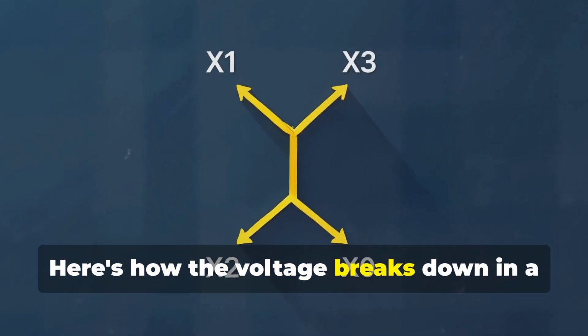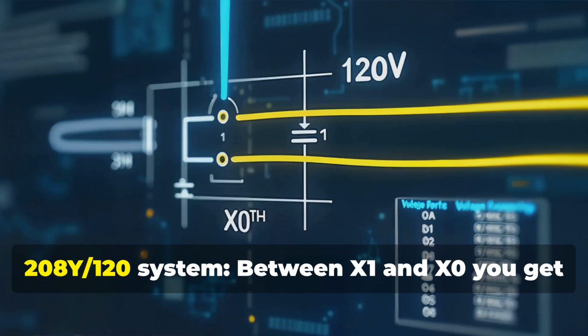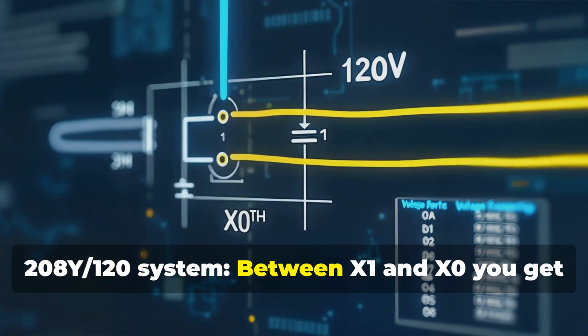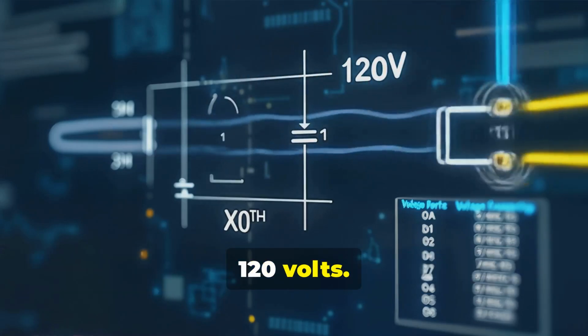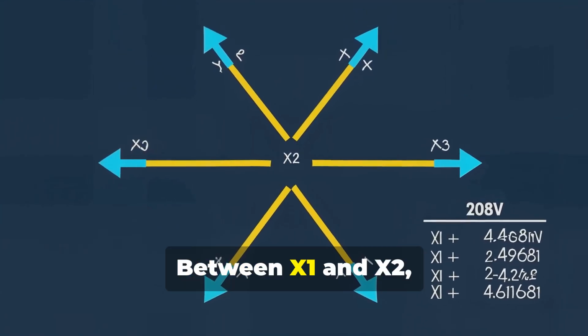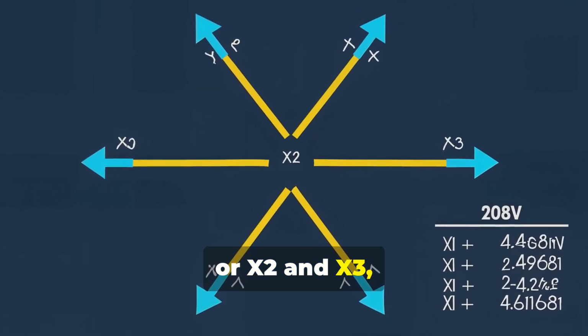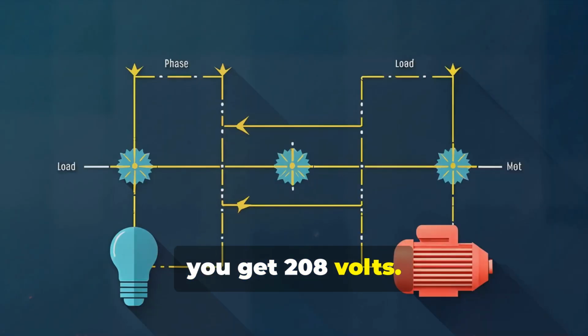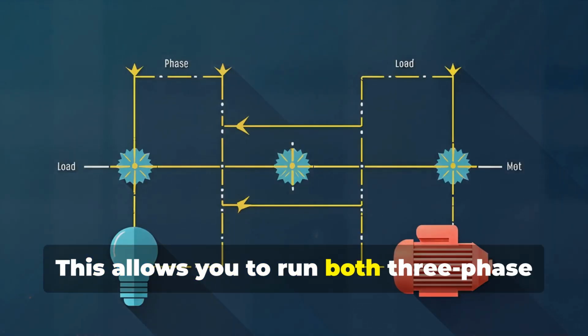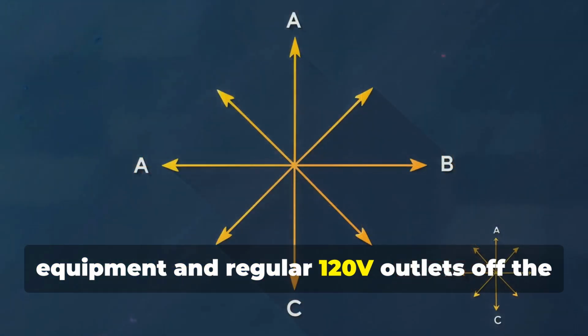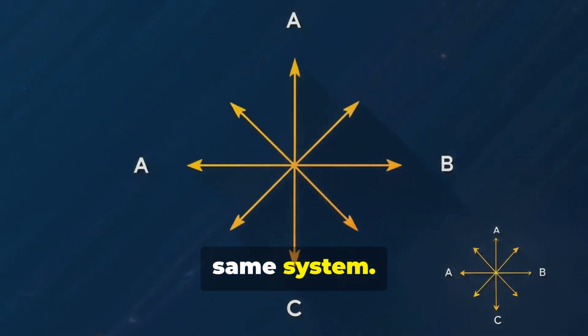Here's how the voltage breaks down in a 208Y/120 system. Between X1 and X0, you get 120 volts. Between X1 and X2 or X2 and X3, you get 208 volts. This allows you to run both three-phase equipment and regular 120V outlets off the same system.